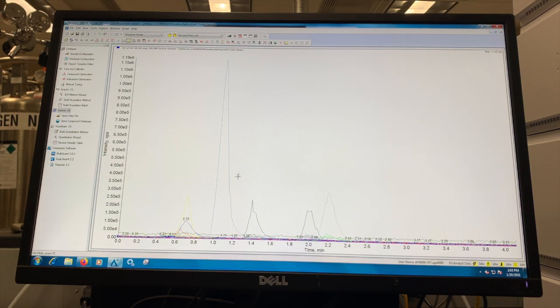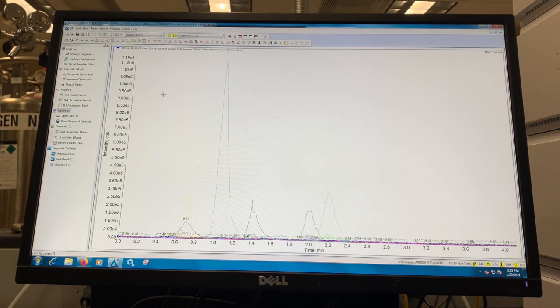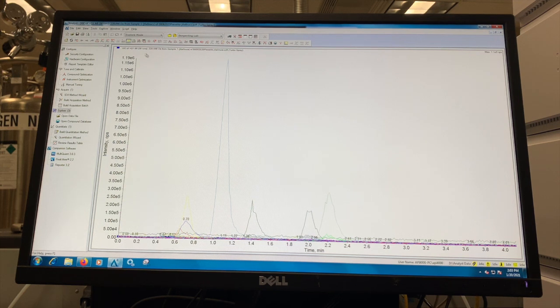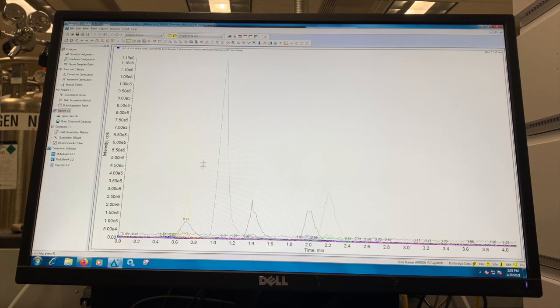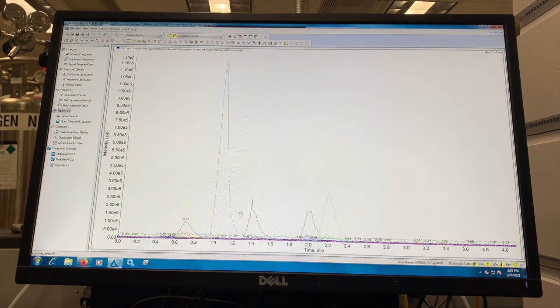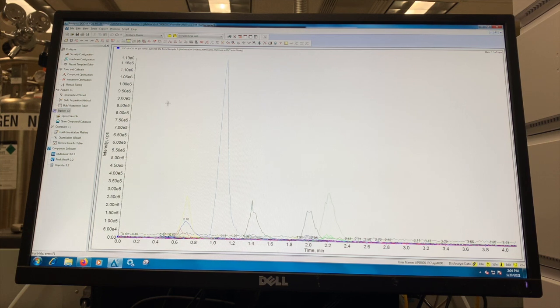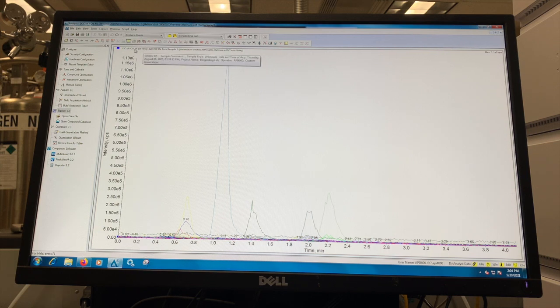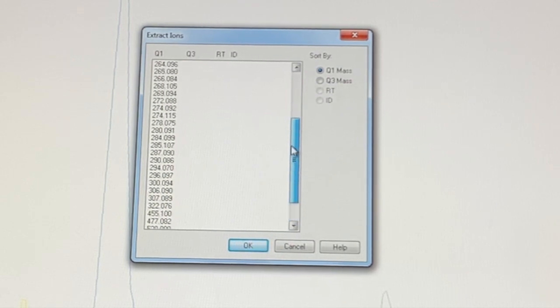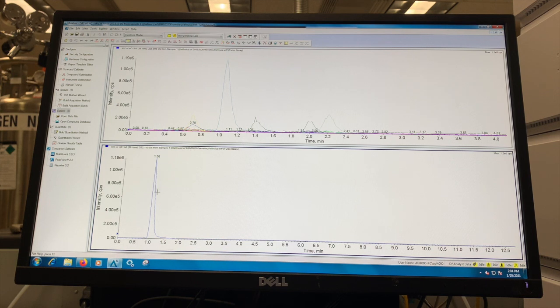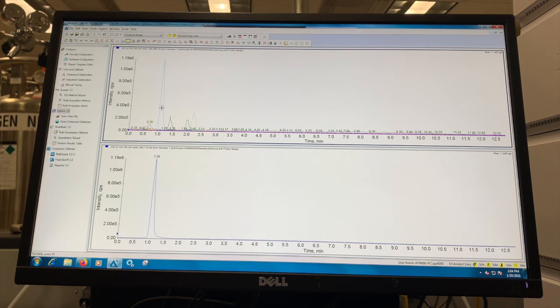This is an example of the data readout from a selected ion mode method. In this case, we use the Q1 multiple ions scan type. And we scan 38 separate ions, which can be seen up here in the upper left. And I hope you can see that there are different colored traces on the chromatogram. And this total chromatogram is an overlay of the individual chromatograms of each of the 38 ions. We can visualize the 38 ions by clicking on the XIC button up top. And these are the masses. And I can even click on one of these masses and it will extract just the chromatogram for that mass. And as we can see, it overlays with this peak in the total ion chromatogram.